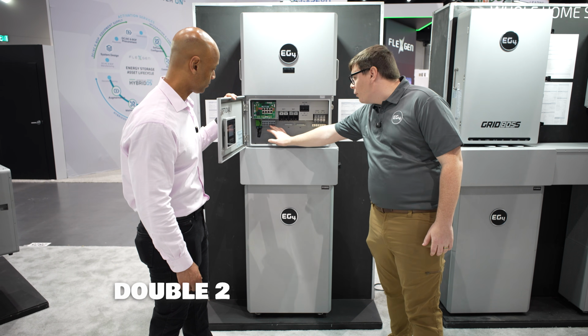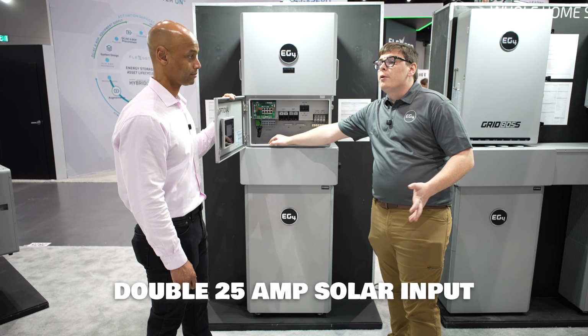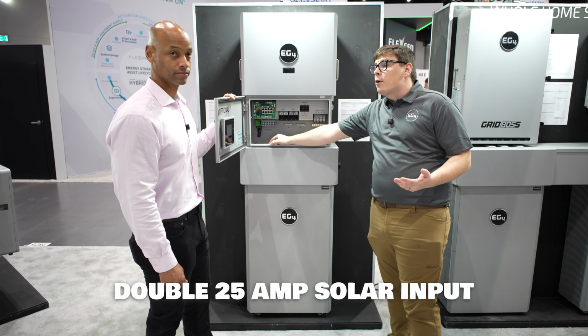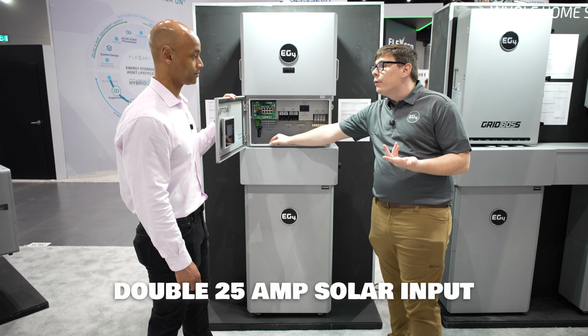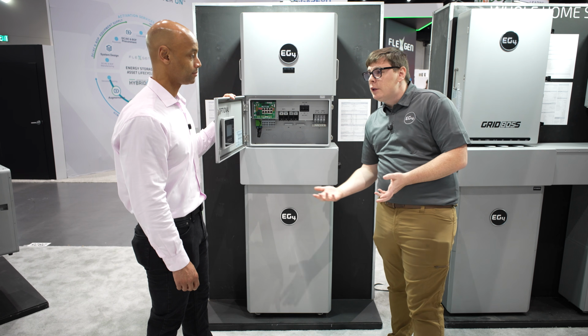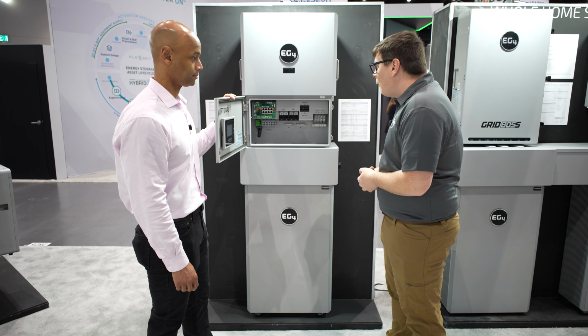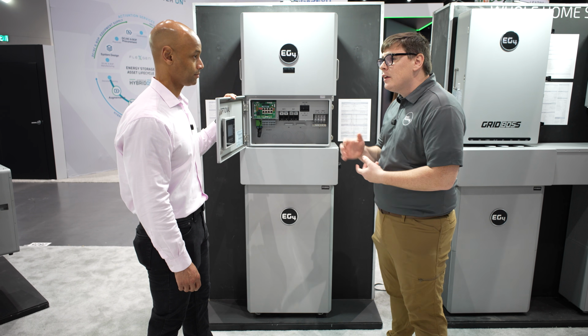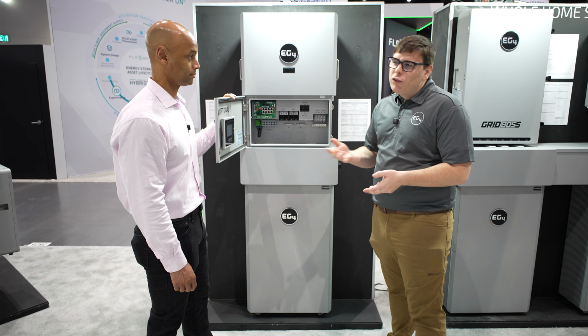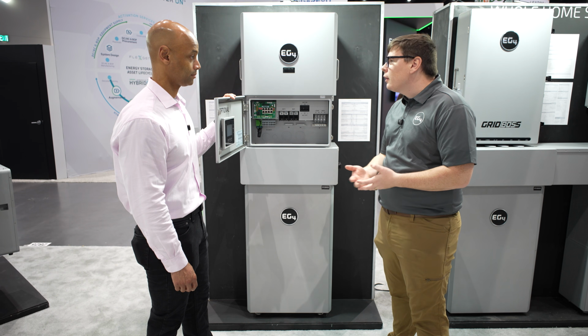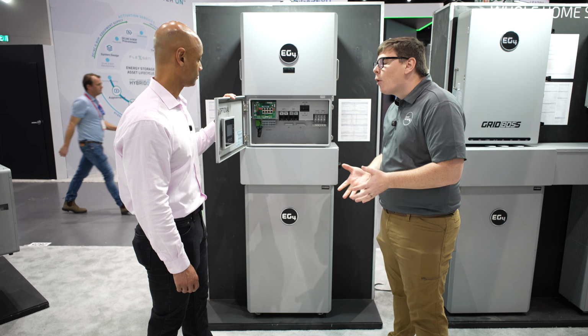So the solar input is a double 25 amp input, so you can do up to 4 strings, 2 in parallel on each input. You won't need a combiner box, you won't need fuses, which are points of failure. And it'll handle about 18 kilowatts usable, so you could probably run 21 kilowatts nameplate or so into the inverter, no problem.